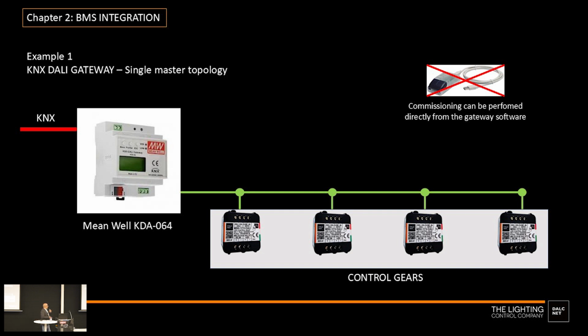And I say that it's a very critical integration because from our experience it is where we can have many different possible compatibility issues. One of the main reasons is that this kind of devices most of the time are managed by companies that don't know anything about DALI. So even if we're speaking about huge companies like, I don't know, Schneider, ABB, or you name it, Meanwell is another one, these companies have a lot of experience in their field, but they don't know anything about DALI. And so when they have to do this kind of accessory, the gateway, they usually rely on a third-party manufacturer. So this configuration is quite typical. And the products, most of the time, work extremely badly. For this reason, I always try to stress this, because the complication is not on the DALI side. The complication is in the way that these devices are made.